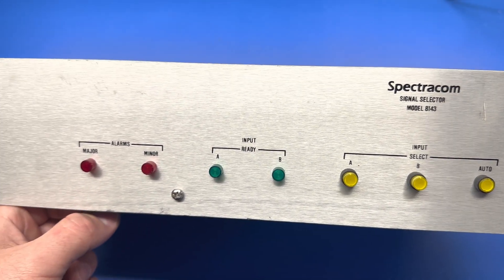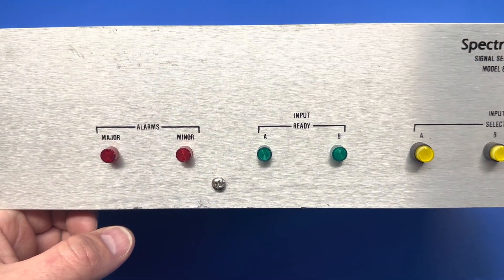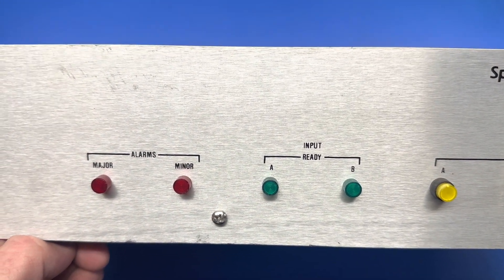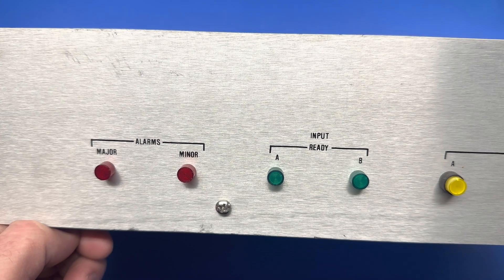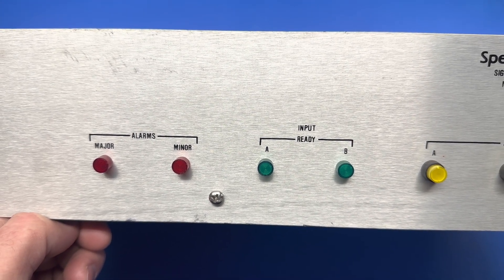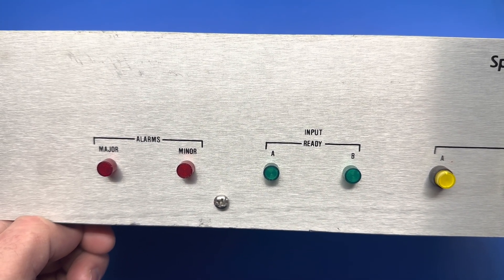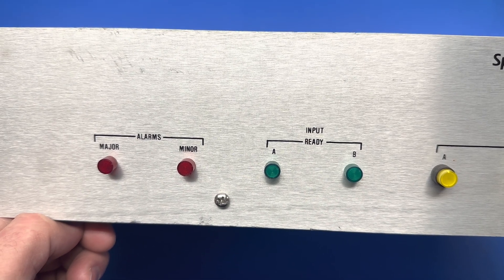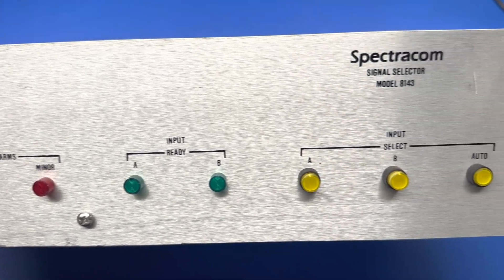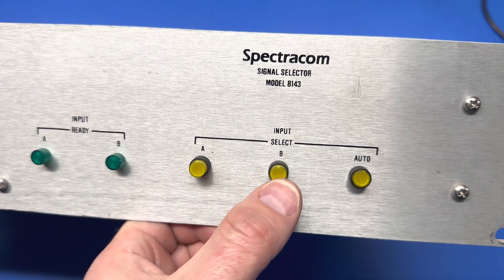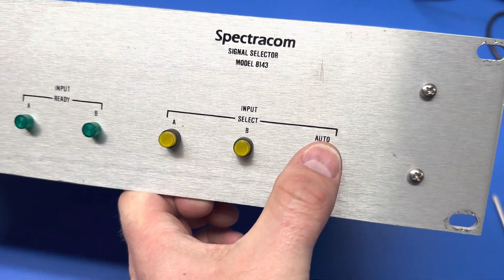The front panel is pretty basic. You've got your alarm. The major alarm goes off if neither of the two frequency inputs are active. Minor alarm will go off if one of the two is out. You can manually select between them by pressing these buttons or you can go to auto.